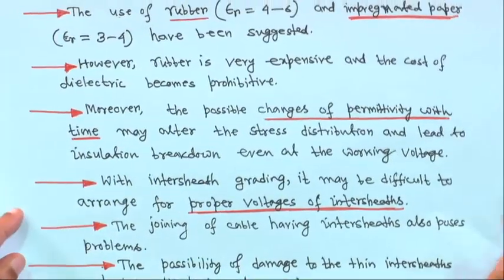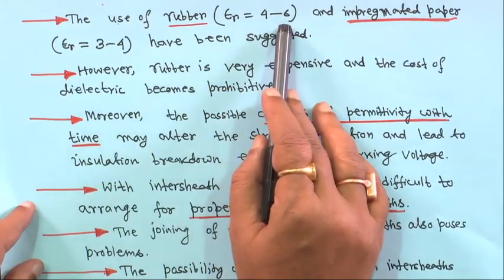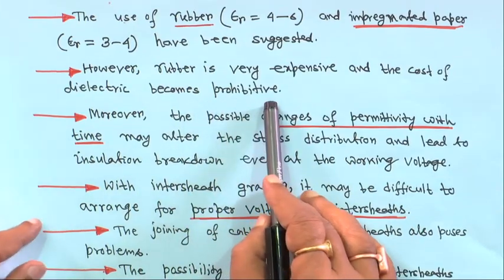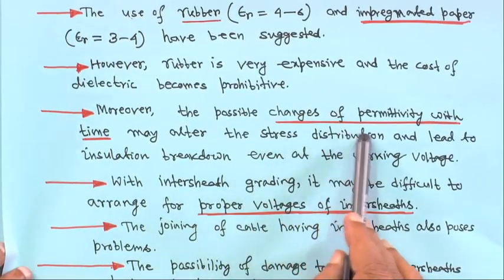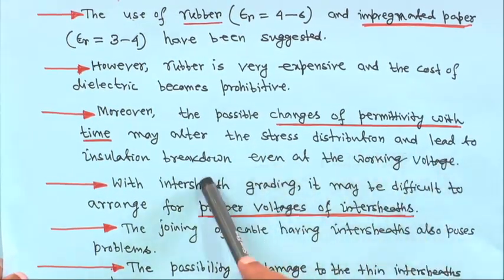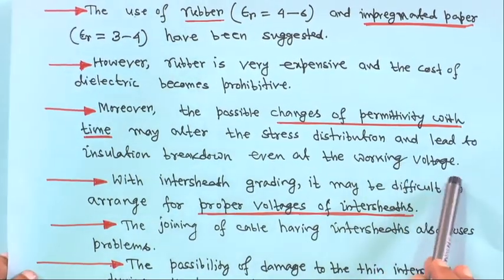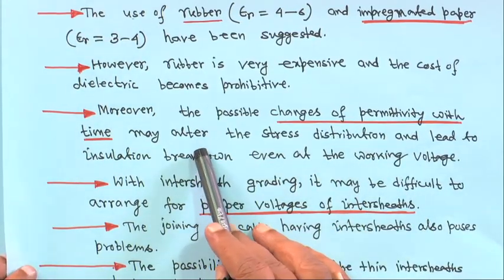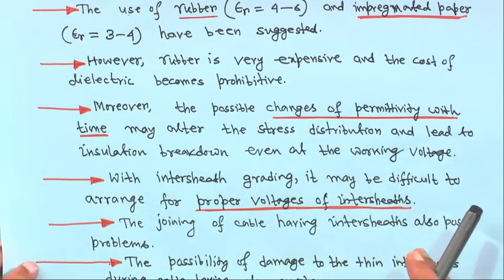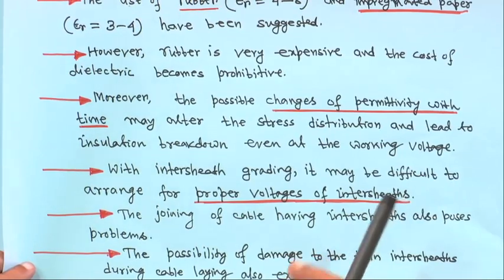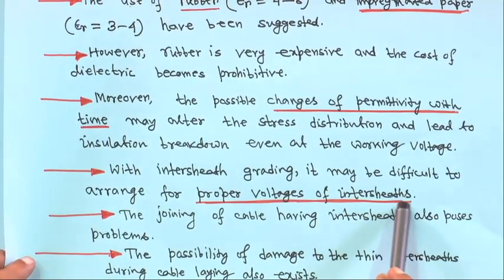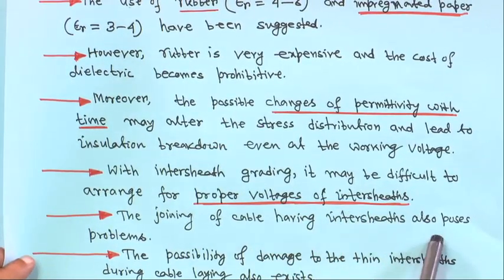Moreover, possible changes in permittivity with time may alter the stress distribution and lead to insulation breakdown even at the working voltage. With intersheath grading, it may be difficult to arrange the proper voltage on the intersheaths since they must be connected to transformer winding tappings, which is a very difficult task.